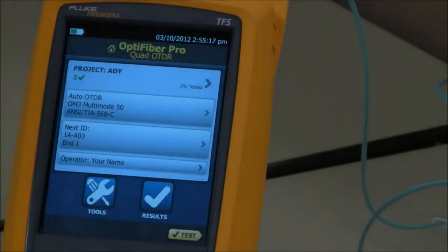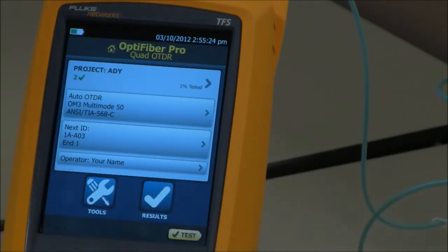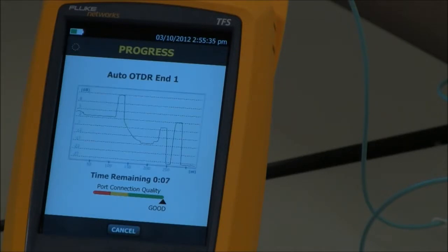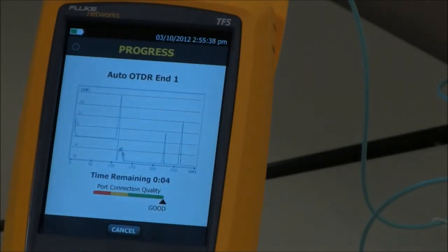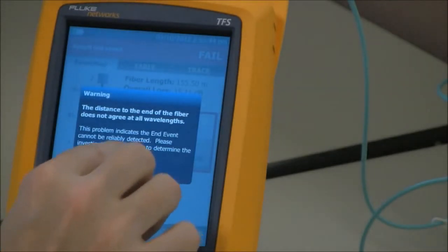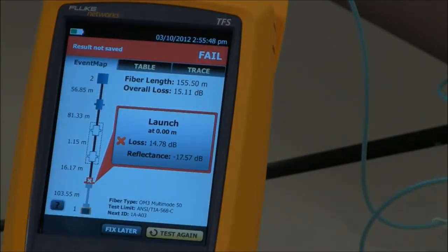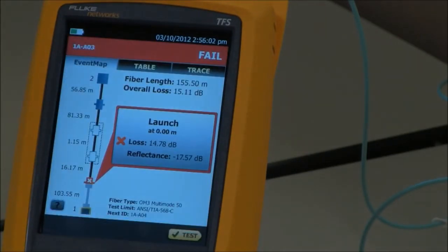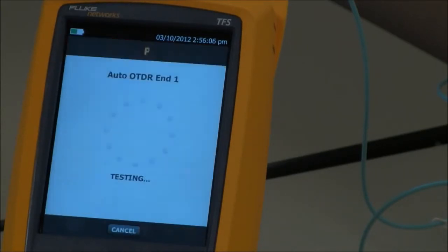If I go to the home screen, I can see two tests are done and 2% has been tested so far. Let me create a fault and run a test. That doesn't look too good — that's not the kind of thing you normally see with an OTDR trace. It's going to give me a warning. It's failed. I've got two options: I can fix this link now and hit test again, or I can just keep testing, which is what I'm going to do. I'll hit fix later, and it will save it as 03. Then I'll move on to my next link.